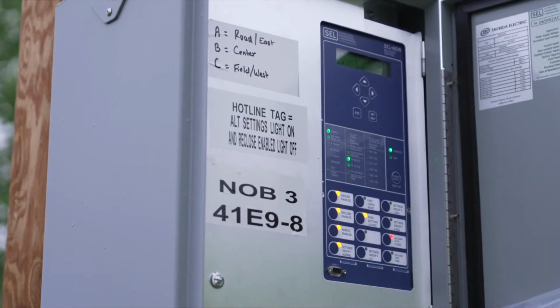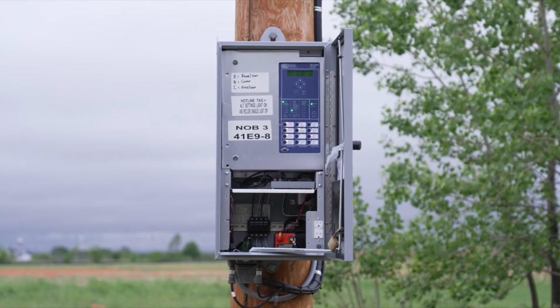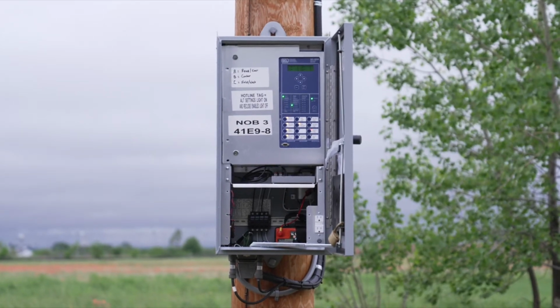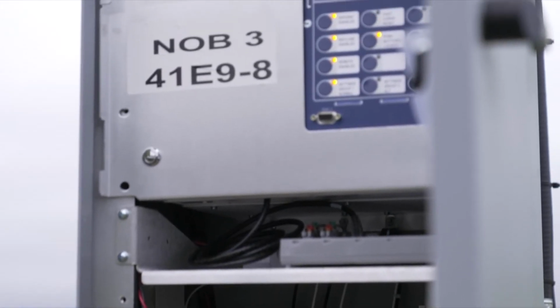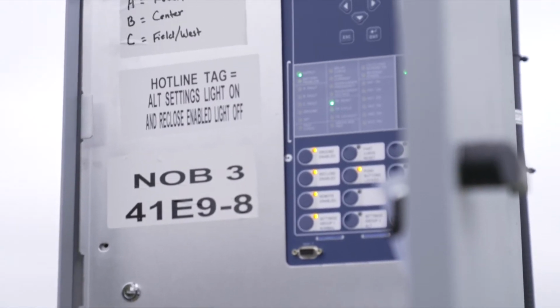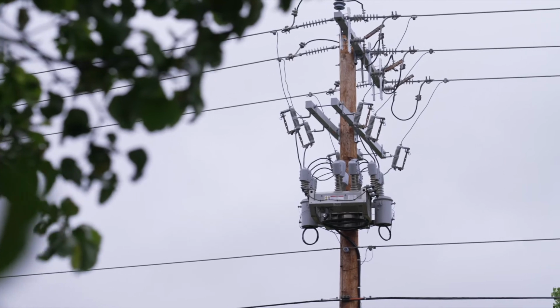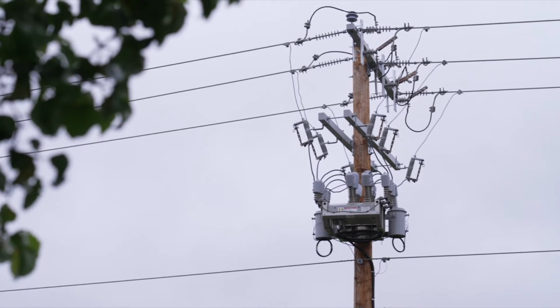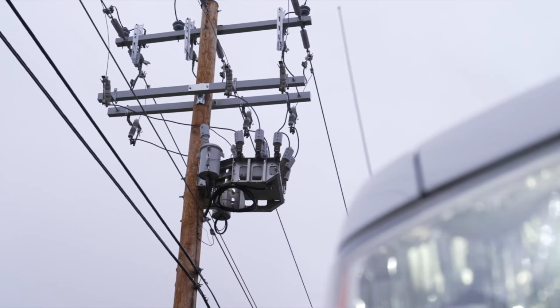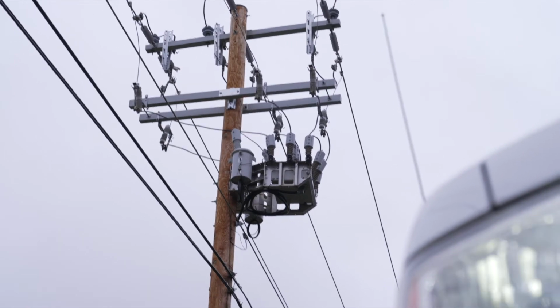So the member will still see a brief interruption of power. A lot of our systems in place allow us to break power for up to 2 seconds and then restore power. 85% of outages that happen in the United States are temporary in nature. Tree branches fall from a tree and hit the line, and if we just disconnect the line before any energy can build and reconnect 2 seconds later, there's an 85% chance that that tree limb has fallen to the ground or whatever was causing an issue has passed.